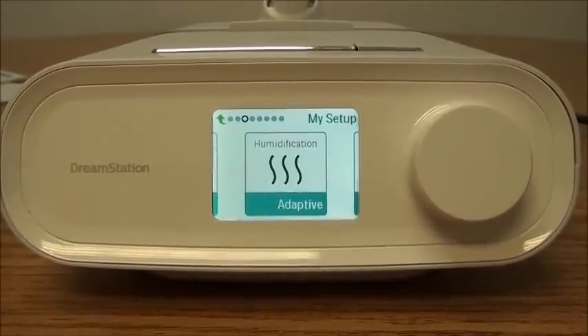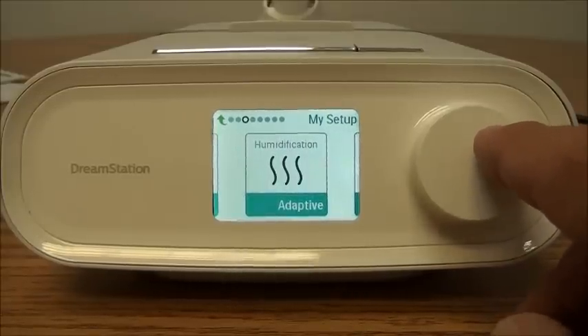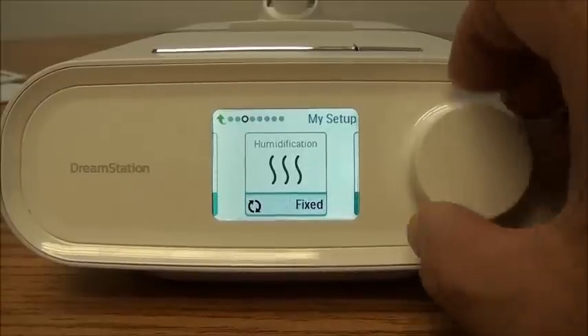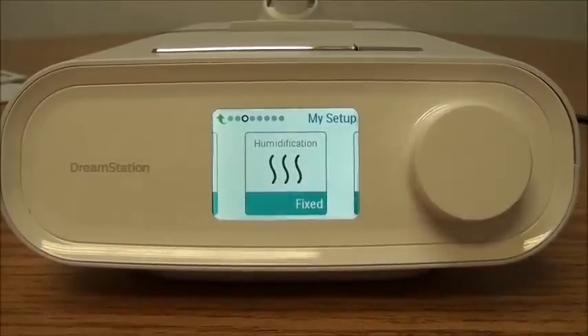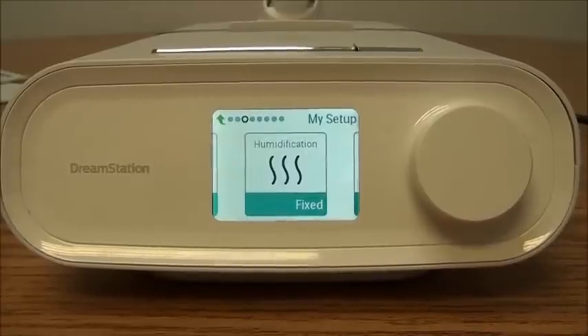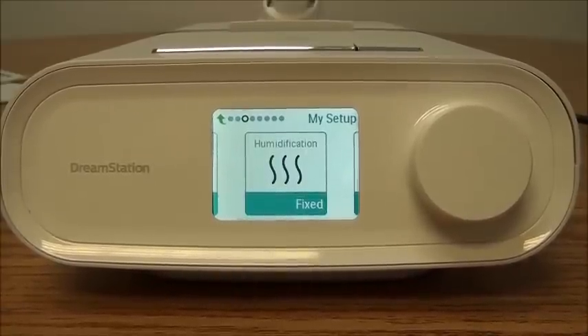Okay, let's talk about humidification. The humidification on this unit can be set up both in an adaptive mode and a fixed mode. The adaptive mode will adjust the heated humidifier to changes in room temperature. And if we wanted to change that, we can just depress the button here, and we can then adjust it into a fixed mode where it will not adjust the heated humidifier to changes in the room temperature.